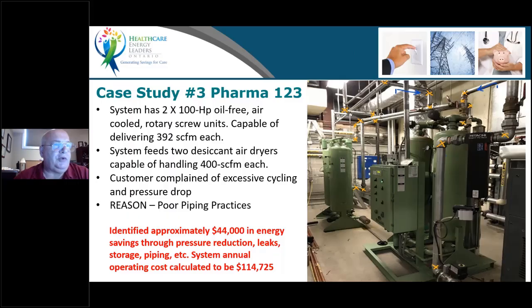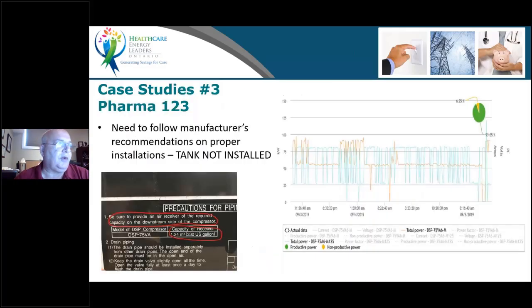They had both dryers online simultaneously purging when only one was required. So there was excessive purging on a second dryer that wasn't necessary. Out of the operating cost of $114,000 per year to run these two compressors, we identified $44,000 in energy savings through pressure reductions, leaks, storage, and proper piping. No other requirements in the system, such as a new compressor, storage tanks, and so on.